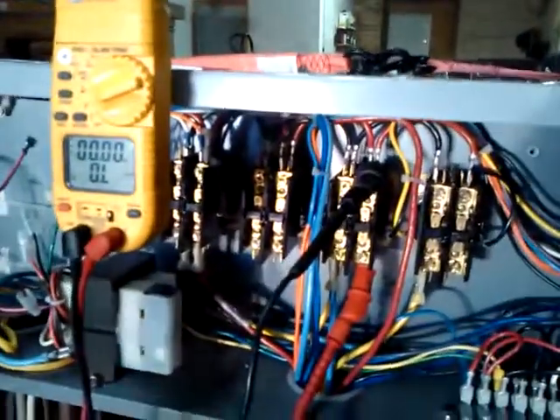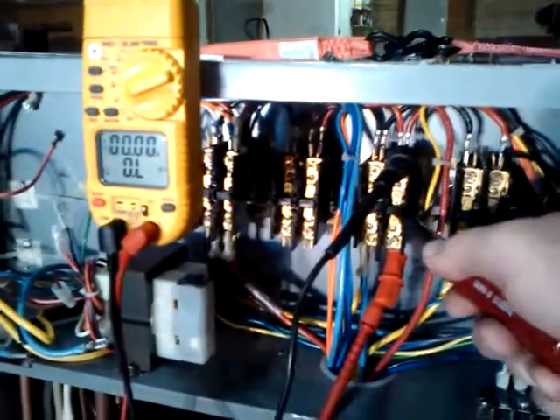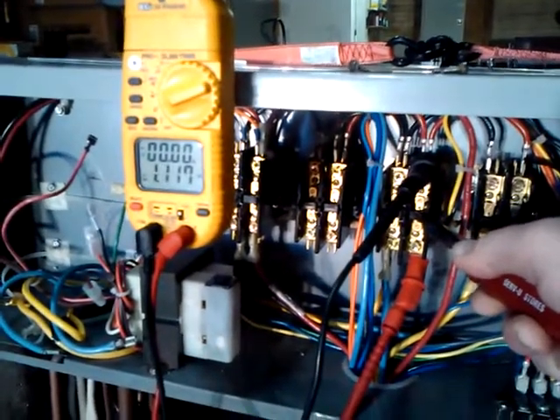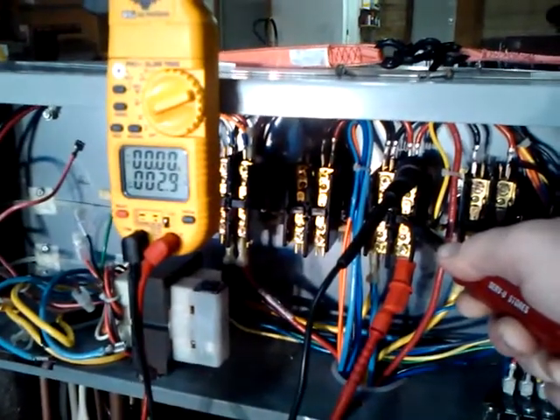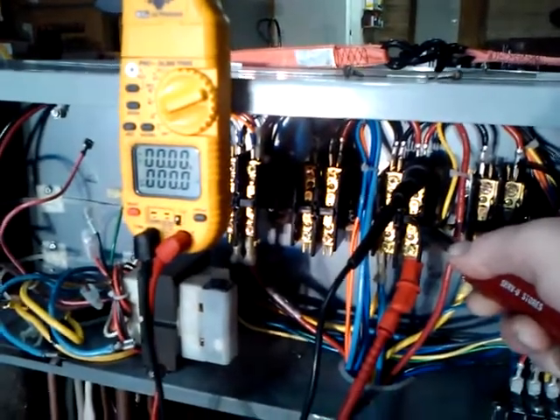We're going to check the primary 1 contactor now, so we're on the L2-T2 side. And again, we're all over the place — that says .029. So we are just all over the place on the right side of the primary 1 contactor here.